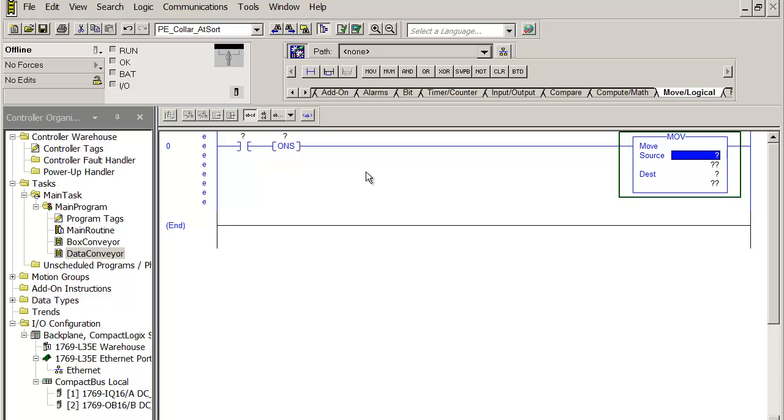When you move something, it's not where it used to be. You moved it to a new location. An MOV instruction, we couldn't call it a copy instruction because that instruction was already used for a file copy, COP. So really an MOV, move, is really a word copy. It copies it from the source word to the destination word. And so we'll put code scanned in here.